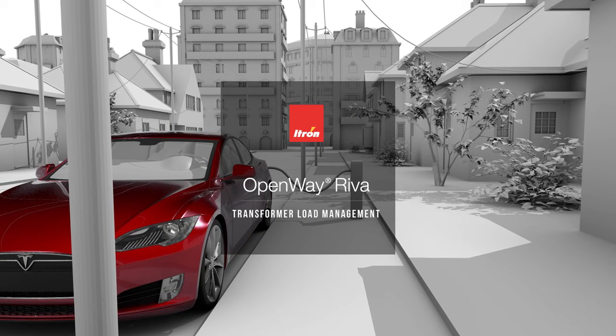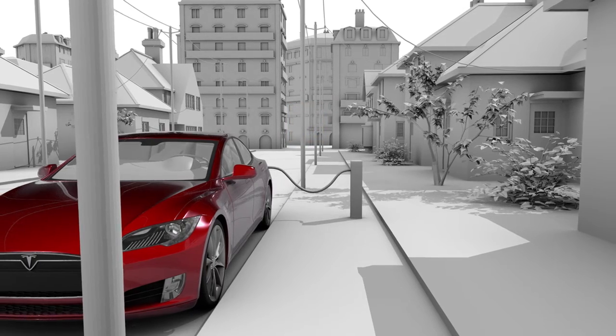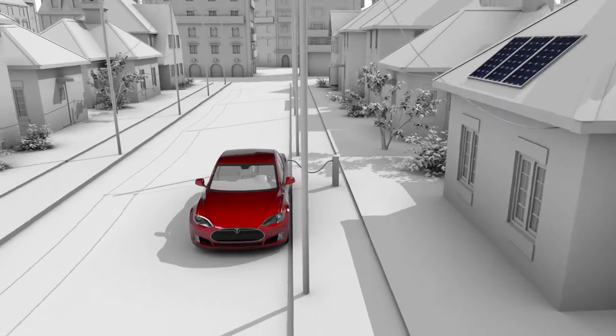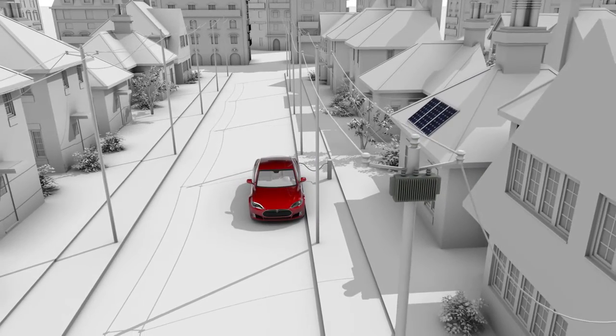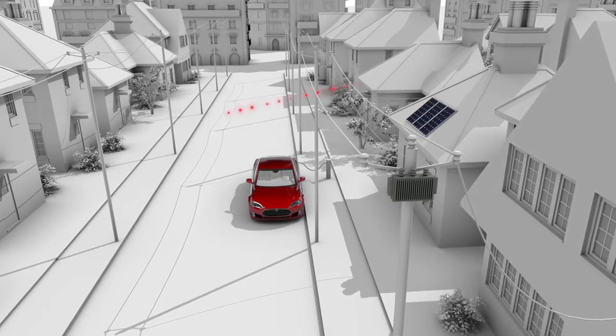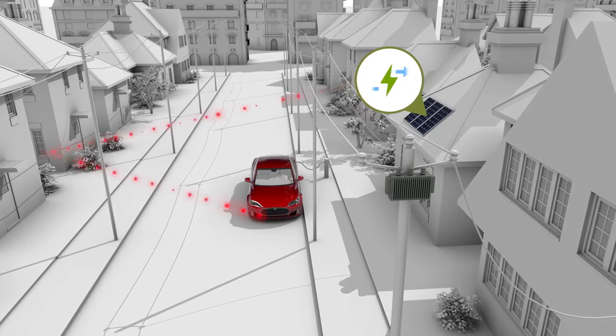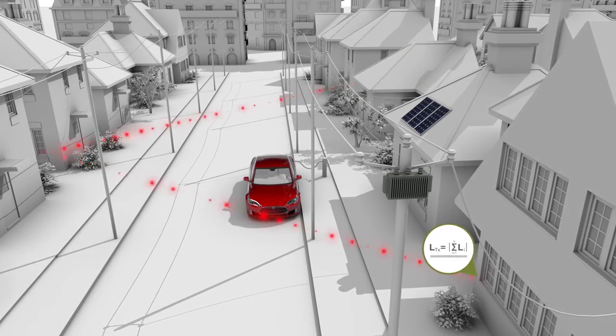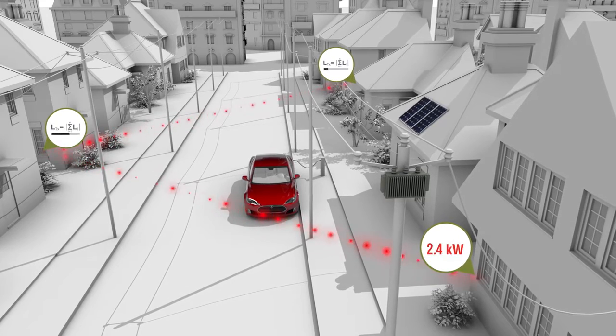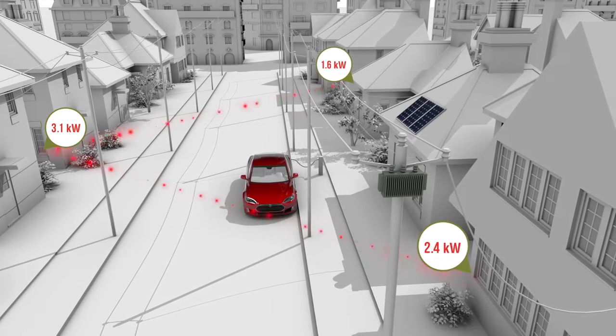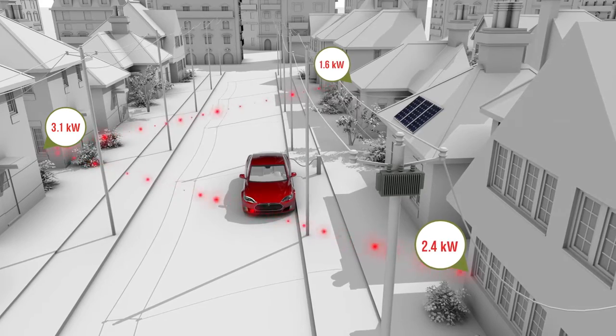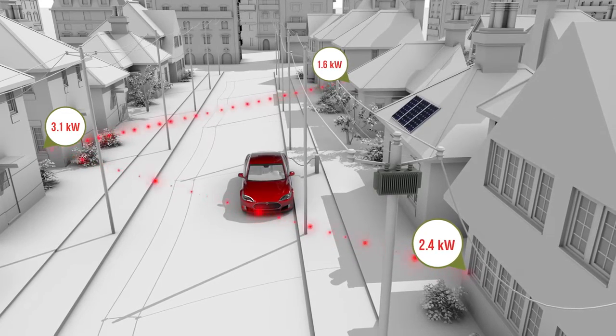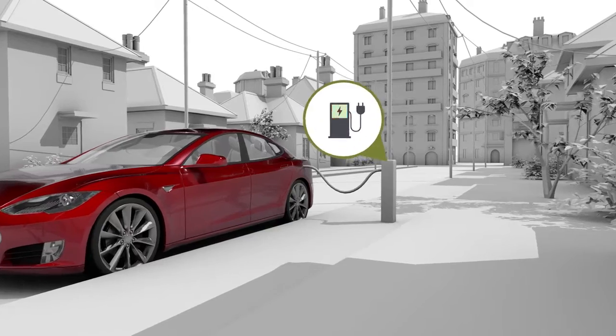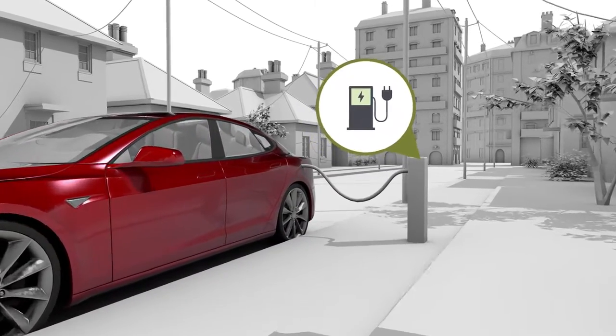OpenWay Riva's Transformer Load Management application reduces the costs, service disruptions, and safety risks associated with overloading transformers. This growing problem is caused by larger loads and the rapid emergence of distributed generation. Only OpenWay Riva continuously calculates and analyzes the load on individual distribution transformers and then manages that load locally and intelligently. OpenWay Riva is continuously aware of which transformer meters are connected to and its rated capacity.